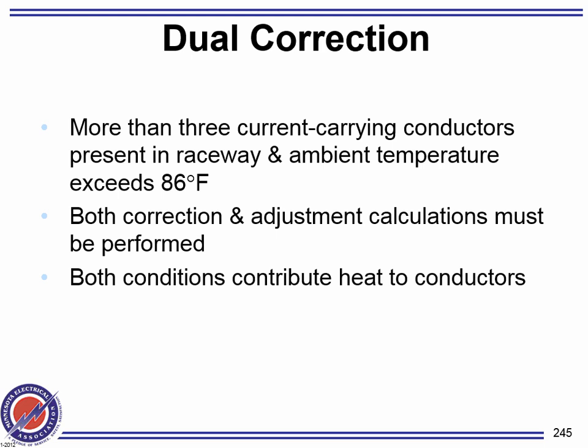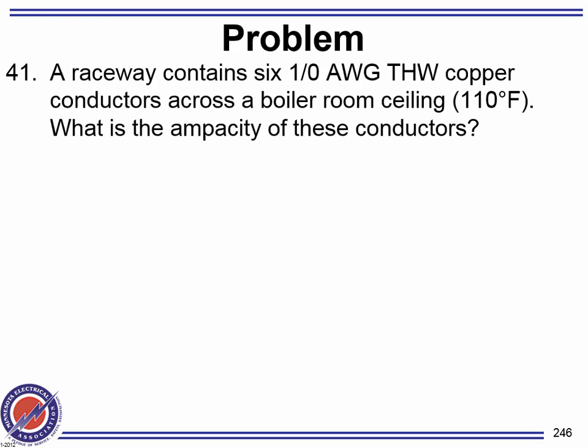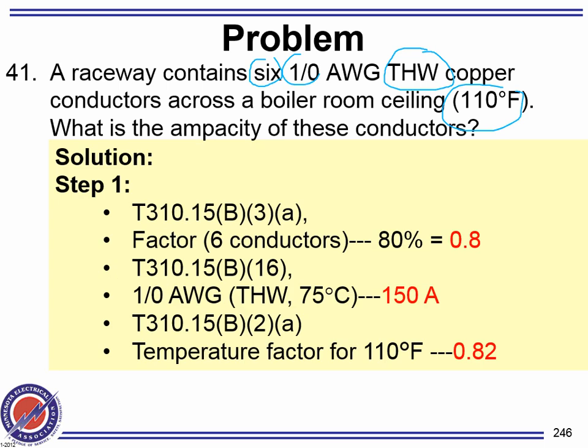Okay, double derating. Double derating is when you have a temperature and a bundling at the same time. No biggie. Okay, so raceway has 6 number 1 aught, and an ambient temperature of this, and an insulation that sucks, THW. How much current can this conductor carry under these circumstances? This is the double hit. You have to cut first because of temperature, then cut second because of what? Bundling. All right. So because of 6 conductors, I have to cut it by 80%. So I lost 20% of my ampacity because of that. Now, because of temperature, I lost another 18%.